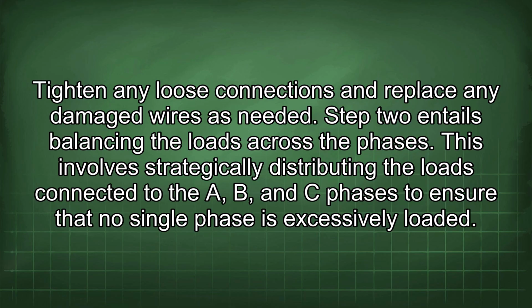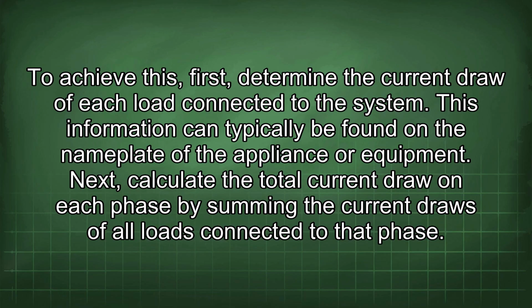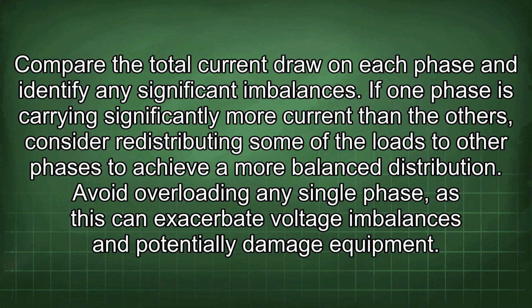Step 2 entails balancing the loads across the phases. This involves strategically distributing the loads connected to the A, B, and C phases to ensure that no single phase is excessively loaded. To achieve this, first, determine the current draw of each load connected to the system. This information can typically be found on the nameplate of the appliance or equipment. Next, calculate the total current draw on each phase by summing the current draws of all loads connected to that phase. Compare the total current draw on each phase and identify any significant imbalances.